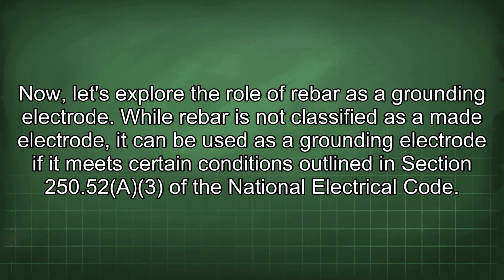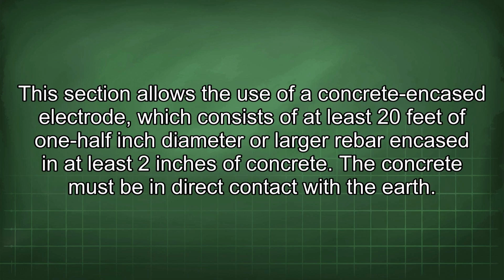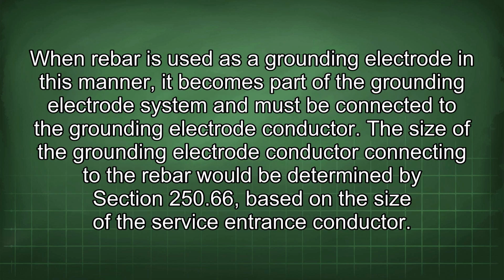Now, let's explore the role of rebar as a grounding electrode. While rebar is not classified as a made electrode, it can be used as a grounding electrode if it meets certain conditions outlined in Section 250.52(A)(3) of the National Electrical Code. This section allows the use of a concrete encased electrode, which consists of at least 20 feet of 1/2 inch diameter or larger rebar encased in at least 2 inches of concrete. The concrete must be in direct contact with the earth. When rebar is used as a grounding electrode in this manner, it becomes part of the grounding electrode system and must be connected to the grounding electrode conductor.